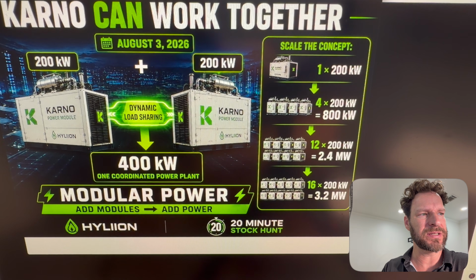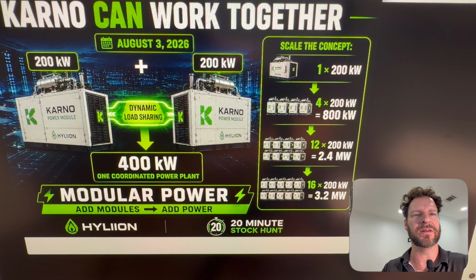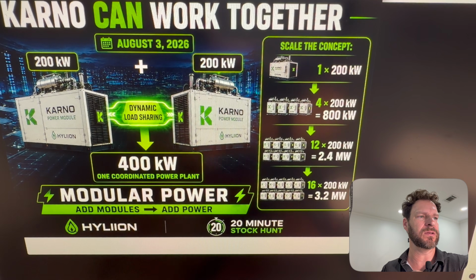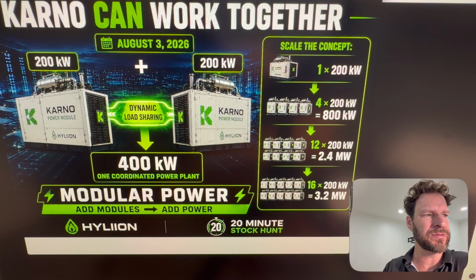The demonstration used two 200 kilowatt Karno units and put them together to make 400 kilowatts. But simply connecting two generators isn't the interesting part. The important part was what happened when electrical demand changed. The two Karno units automatically shared the changing load while maintaining stable power.